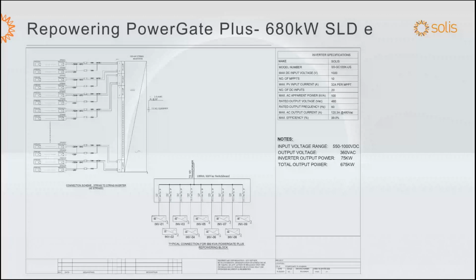The same thing with the 680 kilowatt, same idea: multiple strings, up to 40 strings per inverter, depending on the combiner box. We replace the combiner box and then have a switchgear that combines all 9 inverters and runs at 360 volt AC directly to the transformer.